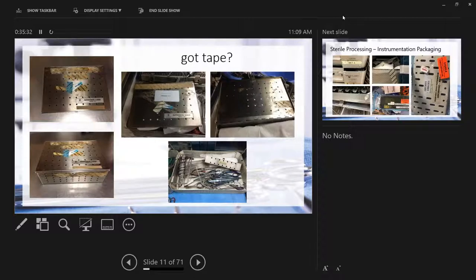So that's just your first indicator. But tape is not supposed to be used on your baskets and internal components. So look—this is three different clients. This picture, let's see which one it is... yeah, this is the same client. The reason there are two is I wanted you to see that it's not just tape on top, but there's tape on the side. This was a separate client. They're using a sticker rated to be sterilized, so that's okay. That's probably a tracking system, maybe SCM or something similar, and that's fine—but this autoclave tape is not okay.